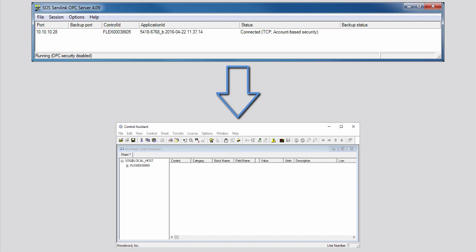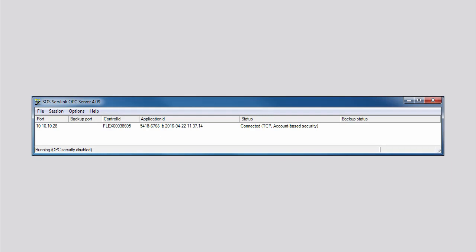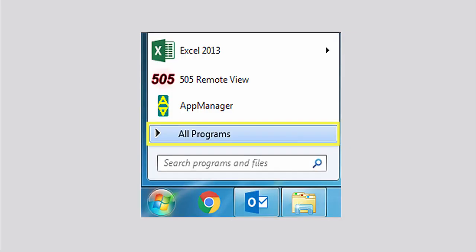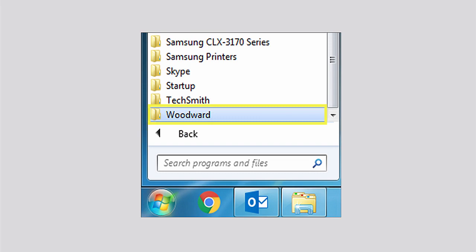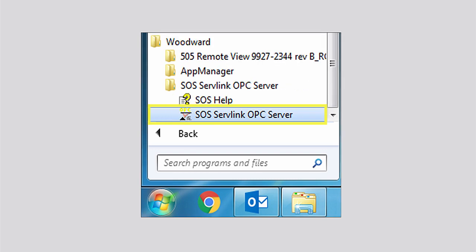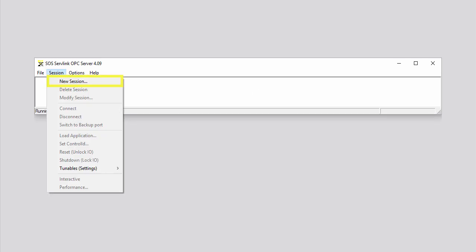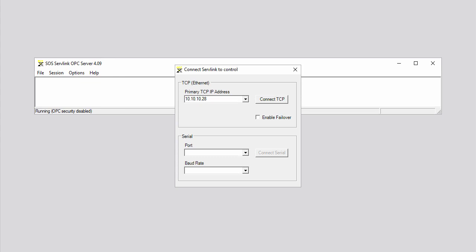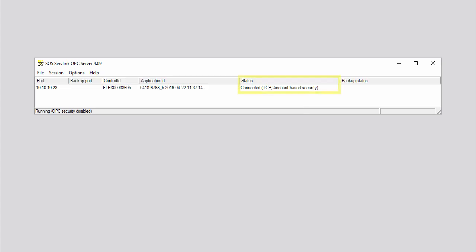The first step toward using SOS Servlink OPC server and Control Assistant is to connect the controller to the OPC server. To do this, open the SOS Servlink OPC server program. Click the Start button, click All Programs, click to open the Woodward folder or, if applicable, the alternate folder you specified during installation. If applicable, click to open the SOS Servlink OPC server folder, then click SOS Servlink OPC server. Click Session on the menu bar, then click New Session on the drop-down menu. In the Connect Servlink to Control window that opens, enter the IP address of your controller in the Primary TCP IP Address box, then click Connect TCP. The Status column identifies that the controller is now connected to the OPC server, the Port column displays the IP address, and the Control ID column displays the name of your controller.